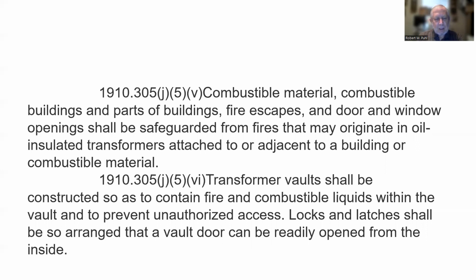Transformer vaults shall be constructed so as to contain fire and combustible liquids within the vault and to prevent unauthorized access. Locks and latches shall be arranged so that a vault door can be readily opened from the inside. And that makes a lot of sense too. If you're in a vault and the door accidentally closes while you're in it, you need to be able to get out. And that's with any building, any door, rather.